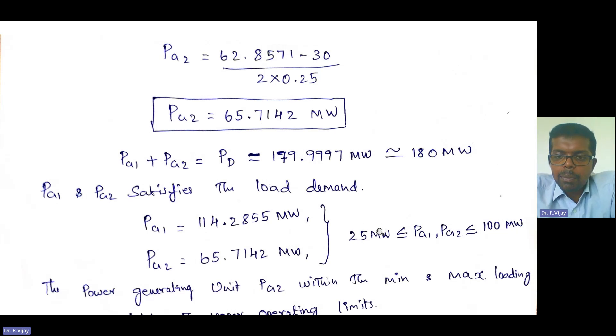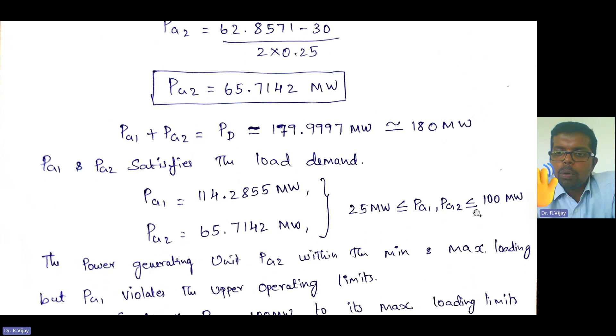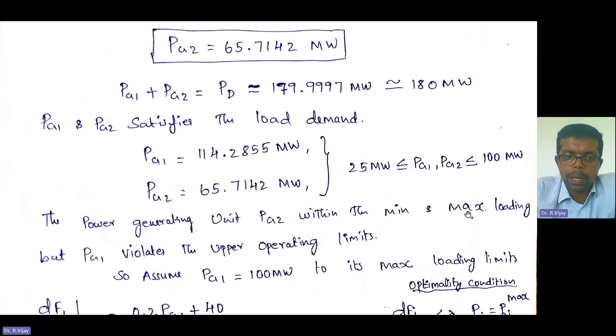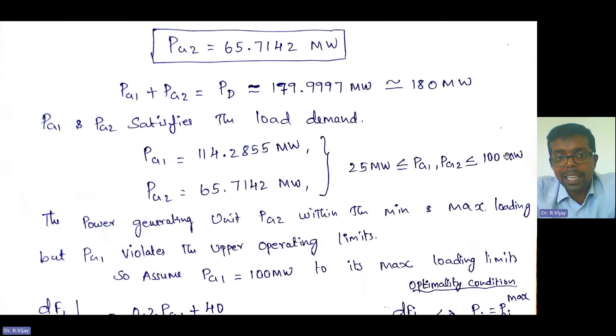Now check the minimum and maximum operating limits: 25 megawatt ≤ PG1, PG2 ≤ 100 megawatt. PG2 satisfies the limit, but PG1 at 114.2855 megawatt violates the upper operating limit of 100 megawatt. So PG1 violates the maximum operating limits.